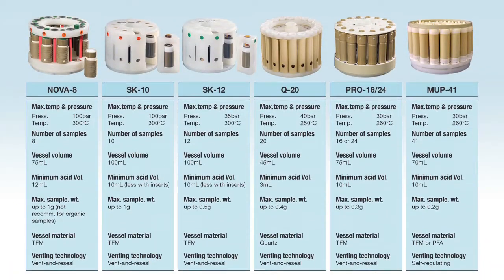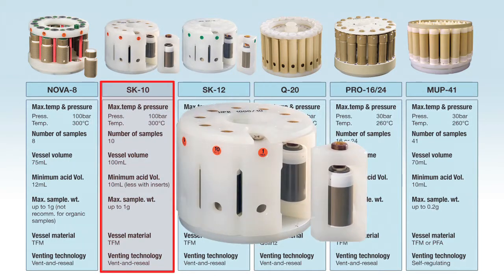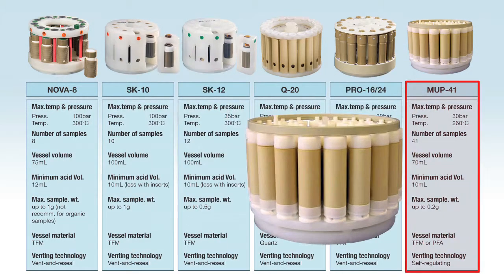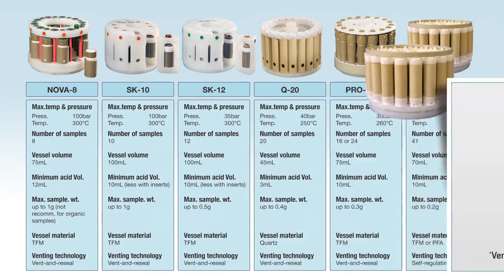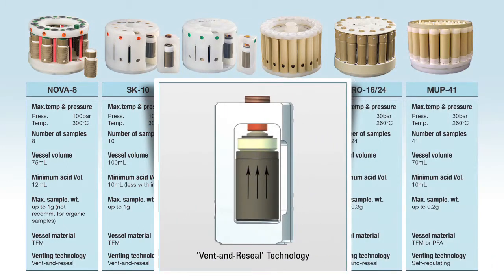The Ethos One has the widest range of rotors and vessels to meet every application, including a 100 bar high pressure rotor and high capacity 41 position rotor. Each of these rotors use Milestone's patented vent and reseal technology and can interchangeably be used in the same Ethos without need for changes or upgrades to the system.